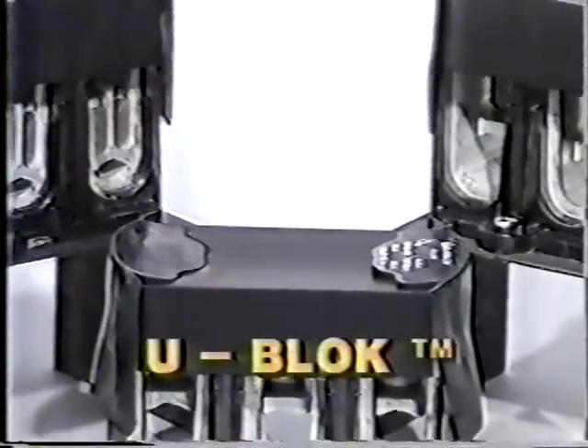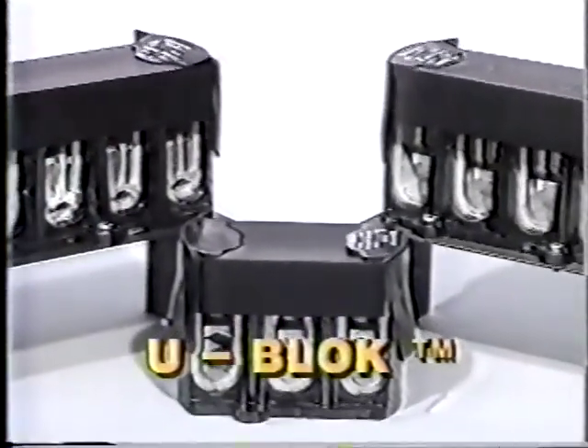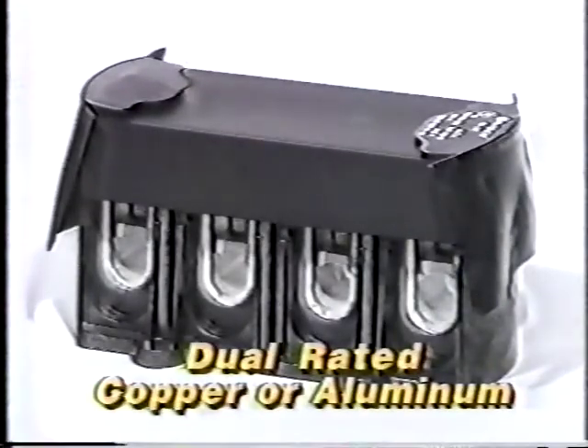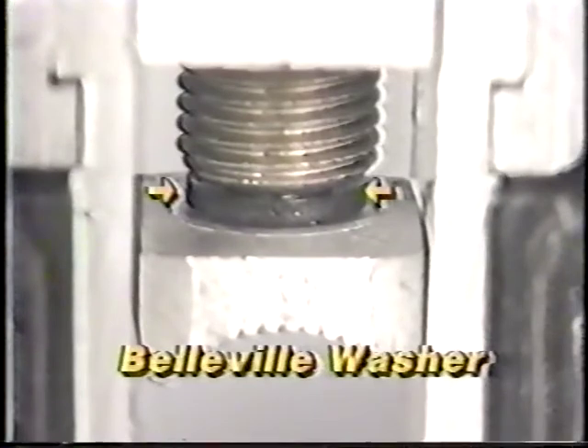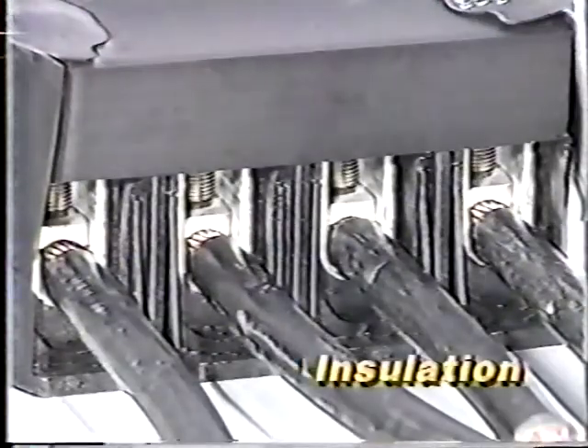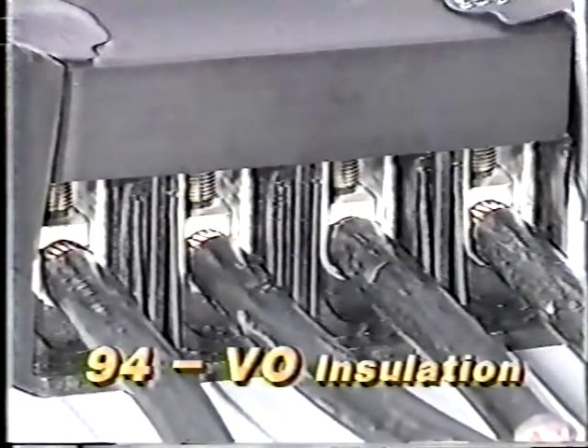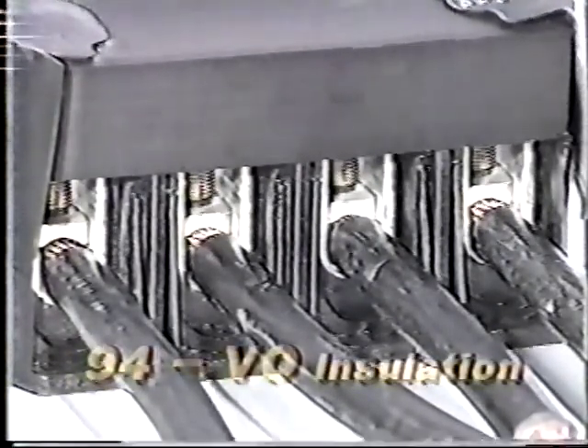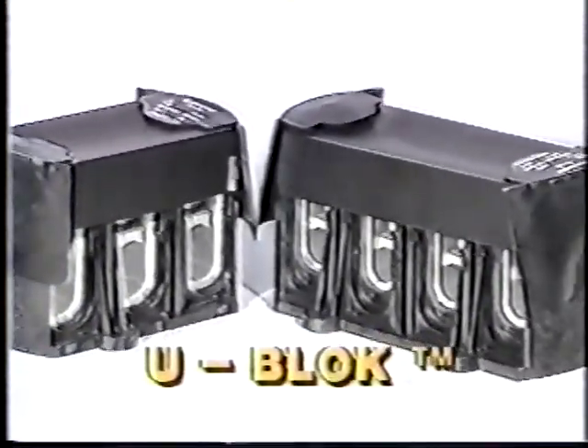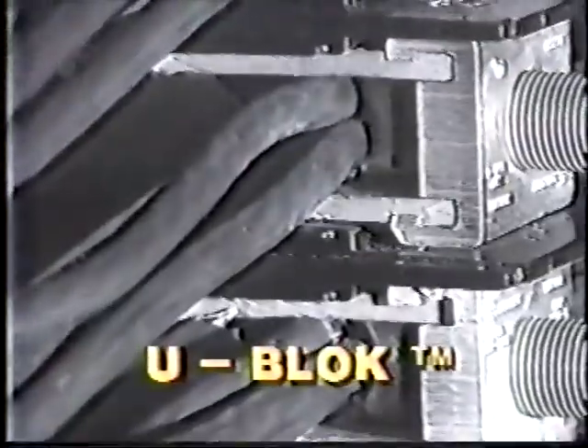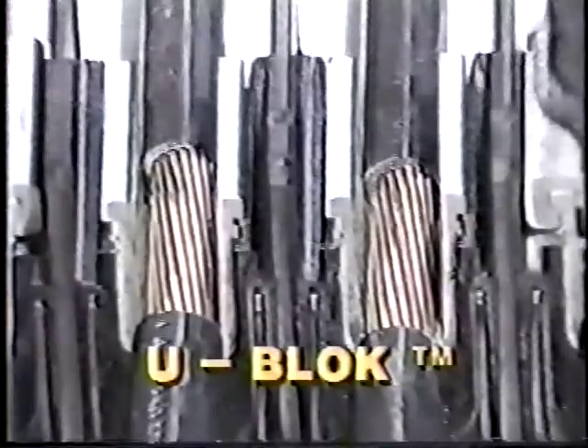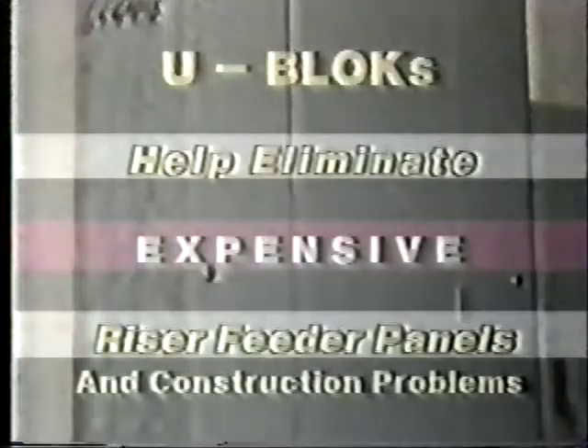Burndy's U-blocks incorporate all of the features found in our U-taps, most notably a dual rating for aluminum or copper conductors, an integral Belleville washer for connection integrity, and our pre-insulated connector housing is rated 94 V-0 to meet or exceed most building codes. Burndy's U-blocks provide an ideal solution to applications such as office condominiums, shopping malls, and even high-rise construction. When used in applications such as these, U-blocks provide an efficient installation, the ability to tap off a continuous uncut riser. U-blocks also help eliminate the need for expensive riser feeder panels and the associated construction problems with their installation.